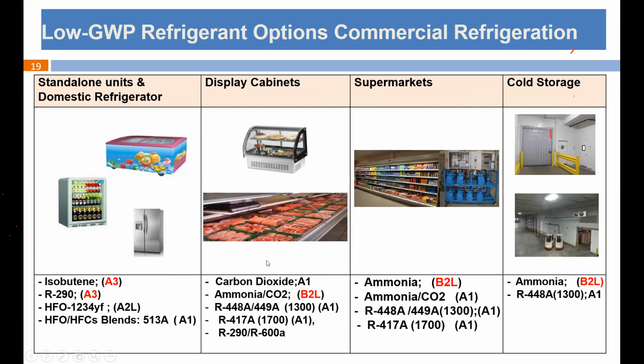For display cabinets for refrigeration purposes, CO2 and a combination of ammonia and CO2. So these are the refrigerants being used. In the case of supermarkets, especially in European countries, there is a lot of use of ammonia, and ammonia CO2 cascading systems are coming into use.